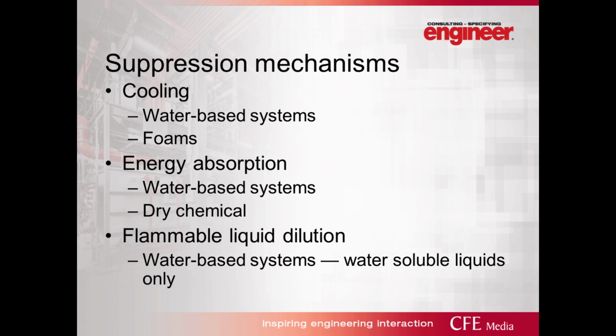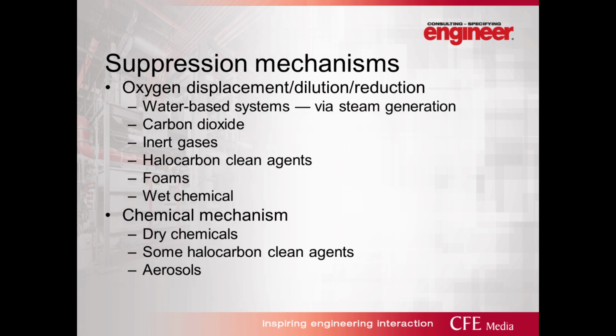Flammable liquid dilution is a very specific type of suppression mechanism. It's only really there for water-based systems and really only works on water-soluble liquids, where the flammable liquid and the water can interact and dilute the whole thing. Insoluble flammable liquids obviously don't work from a dilution standpoint. The water usually drops to the bottom, and the insoluble liquid will stay on top and continue burning because it is still able to get to oxygen.